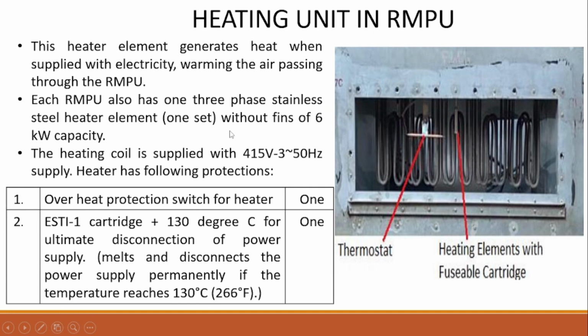Now, the heating unit in the RMPU. The heater element generates heat when supplied with electricity, warming the air passing through the RMPU. The heating coil is supplied with the 415 V supply. The heater has the following protections, as we can see in the chart. The first one is an overheat protection switch for the heater, and the second is an ESTI-1 cartridge plus 130 degrees Celsius, for ultimate disconnection of the power supply if the temperature reaches 130 degrees Celsius.